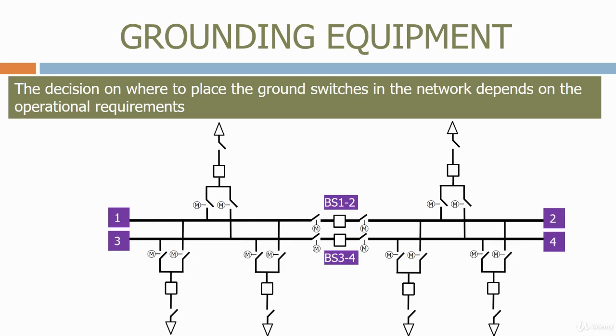Here's a typical double busbar transmission level substation. Let's look at the different parts of the circuit. Firstly, let's look at the busbars. We want to be able to maintain busbar number 1. To do this, we provide a ground switch on busbar number 1. The same requirement applies to all the other busbars.